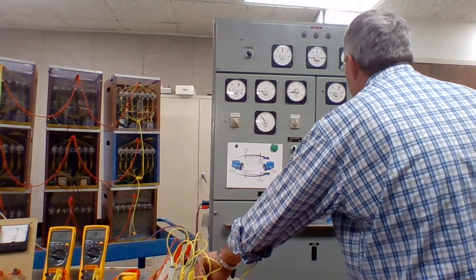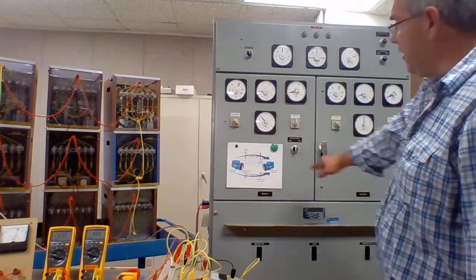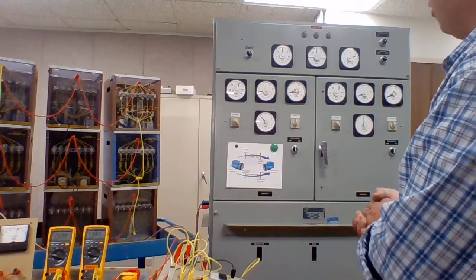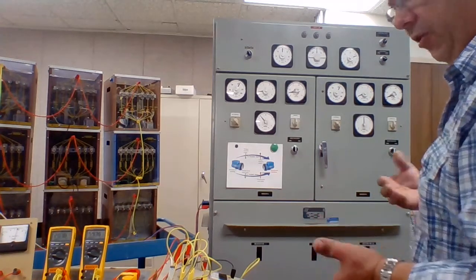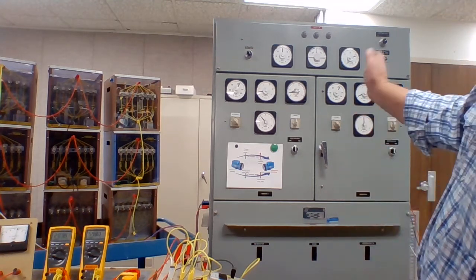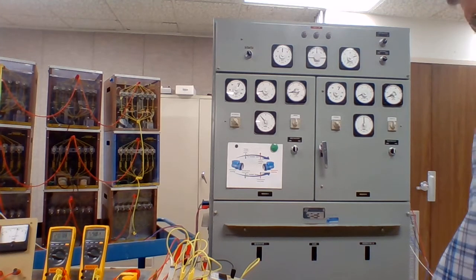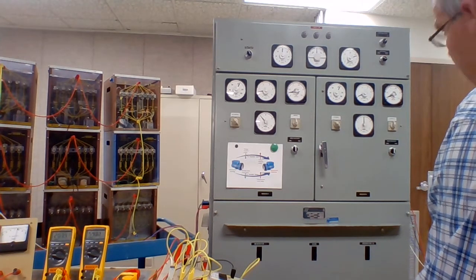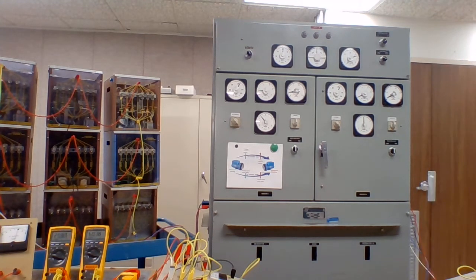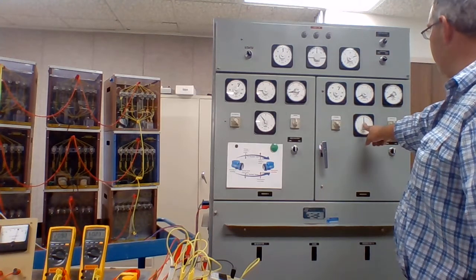If we want to move the VARs back onto this machine, we do the exact opposite — just changing the field excitation. Now we've got no kilovars provided by this one and all the kilovars provided by generator 1. Once they're up and running, you can have whichever alternator providing the majority of power. Right now they're almost equally sharing. Generator 1 is carrying absolutely everything — no kilowatts, no kilovars from generator 2.